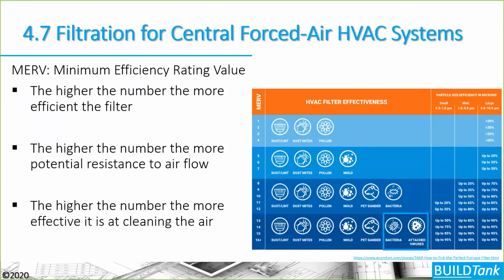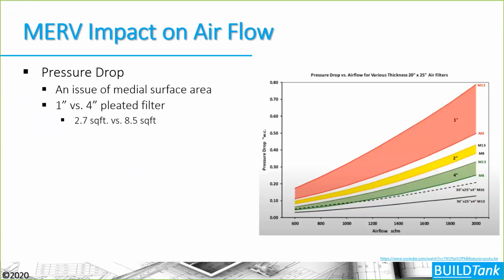The higher the number, the more effective the cleaning of that air is. And you can see here in the picture on the right that you can get filters that actually are able to filter out bacteria and viruses that are in that air. So getting those higher MERV systems can be very worthwhile to consider, but you have to consider what it is doing to restrict the flow of air in that house. So there are some tricks to think about.